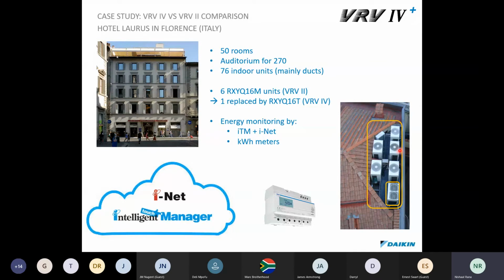If you have 3 condensers on one system, you cannot replace. If they're on one system, so one system meaning that 1, 2, and 3 condensers go into the same pipe run, you cannot change one condenser and leave the other 2. Or you cannot change 2 condensers and leave the other one. You have to change all if they are on the same system. Right? I hope everybody understands that.